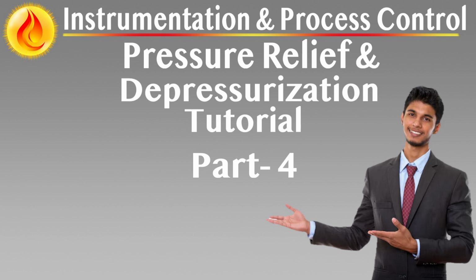Material and construction standards. Pilot burners and supports must be constructed of corrosion-resistant and high-temperature materials. Pilot lines, AISI 321 stainless steel, minimum. Top 4 meters of pilot lines, AISI 310S, Incoloy 800H or equivalent, to withstand direct flare radiation. All thermal expansion and mechanical stresses between pilot lines and the flare stack must be accounted for with appropriate supports and expansion flexibility.